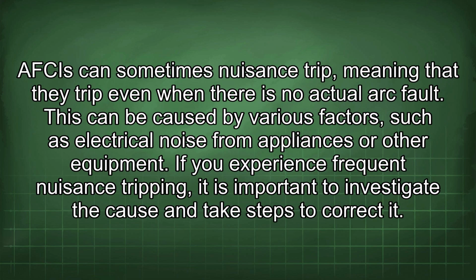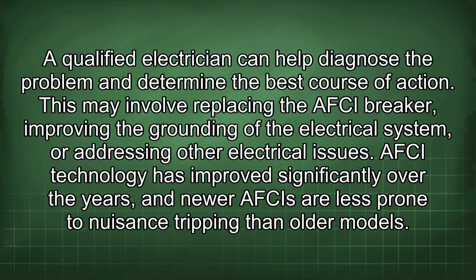AFCIs can sometimes nuisance trip, meaning that they trip even when there is no actual arc fault. This can be caused by various factors, such as electrical noise from appliances or other equipment. If you experience frequent nuisance tripping, it is important to investigate the cause and take steps to correct it. A qualified electrician can help diagnose the problem and determine the best course of action. This may involve replacing the AFCI breaker, improving the grounding of the electrical system, or addressing other electrical issues.